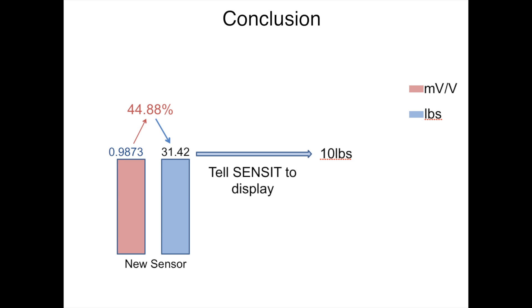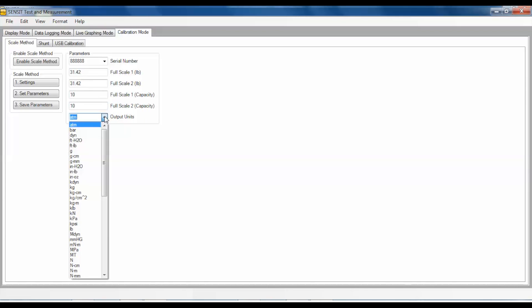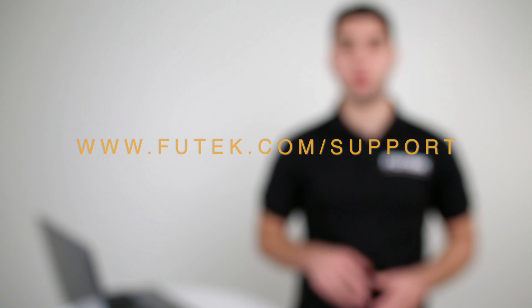So now that we know this information, we can go ahead and fill in our scale method parameters. We found out that at full scale 1, our sensor is only using 31.42 pounds of the 70 pound range. Since we did not have another direction, the 31.42 pounds can go for the negative direction as well. From our calibration certificate, we know that our sensor only has a full capacity of 10 pounds, so we will substitute 10 pounds for the negative direction as well. Our output units found on the calibration certificate were pounds, so we will designate pounds in the output units as well. You can now use the scale method feature by pressing the Enable Scale Method button. For more manuals and support about USB calibration and wiring, please visit our website at www.futek.com/support.